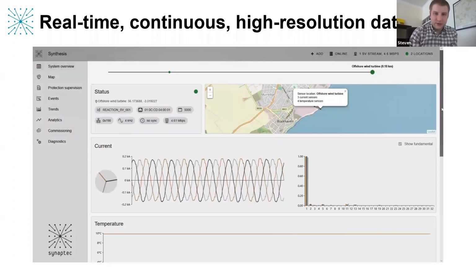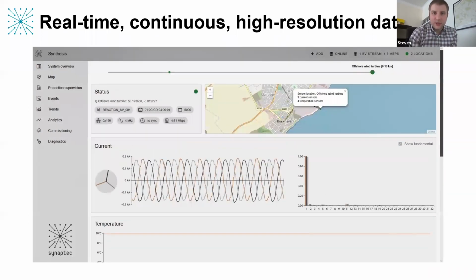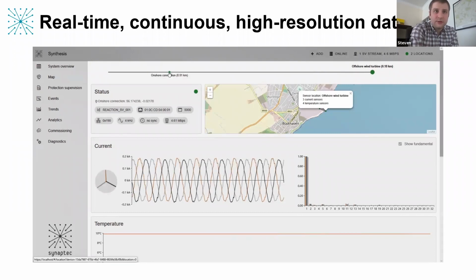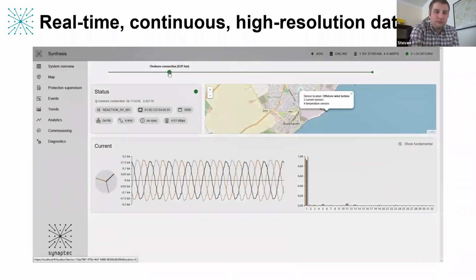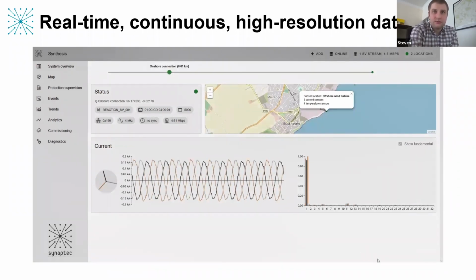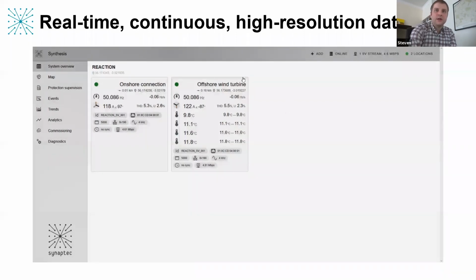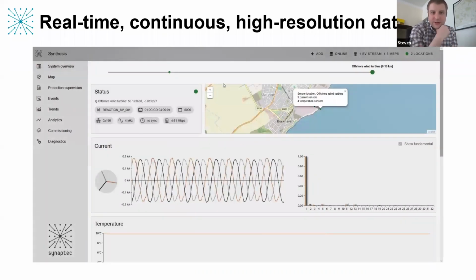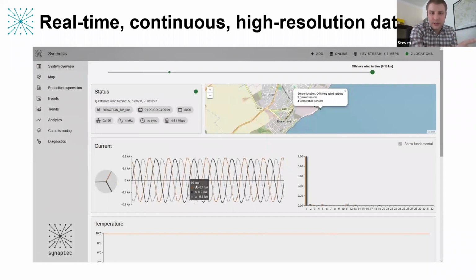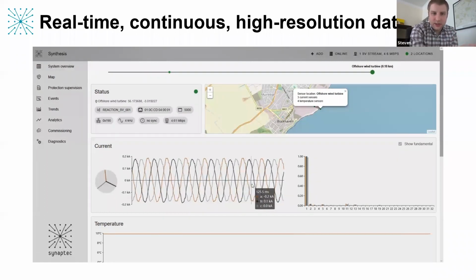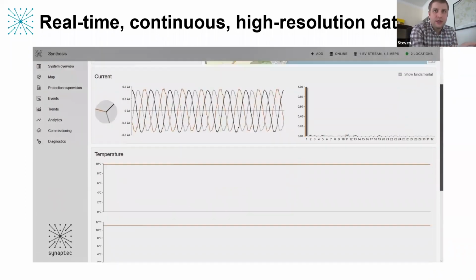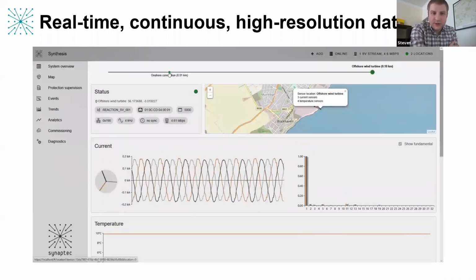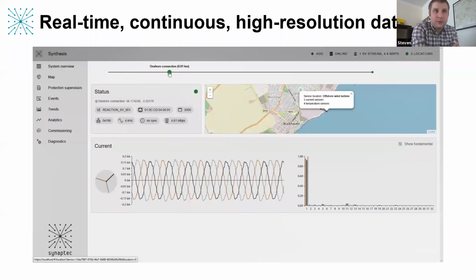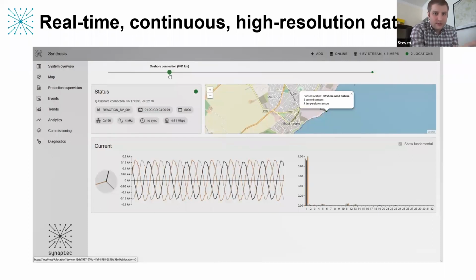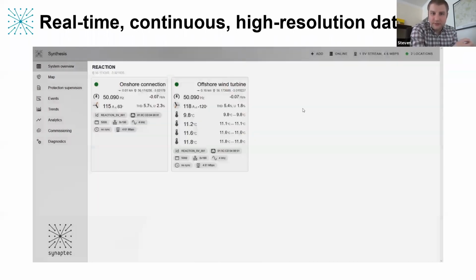Hopefully this gives you an idea that it makes it quite easy and feasible to perform condition monitoring with very granular data. We can pick up very fast electrical transients that you wouldn't normally see in a typical SCADA system. For example, electrical arcing: we see the full detail of these kinds of phenomena, and electrical arcing is something that could affect the long-term health of assets.